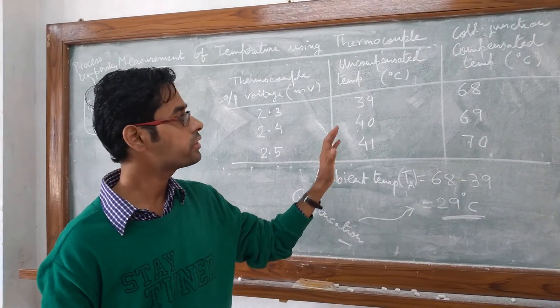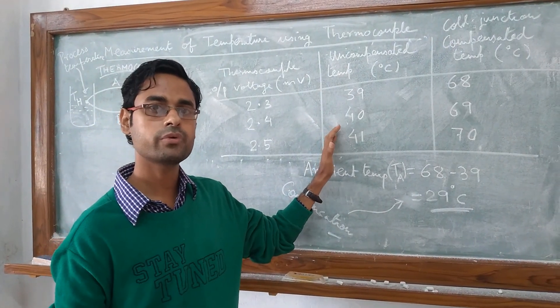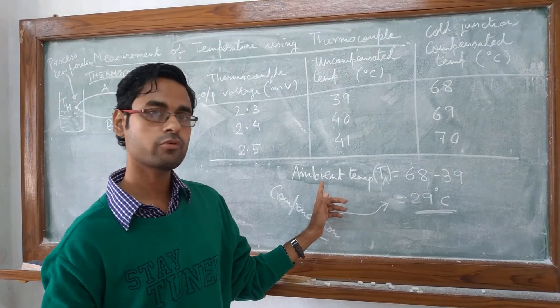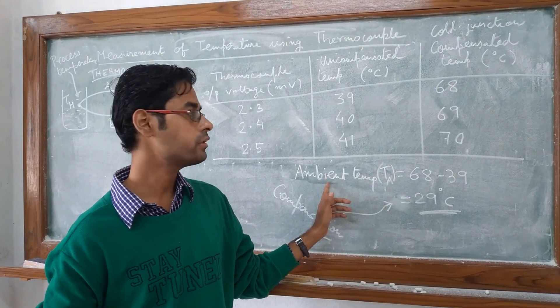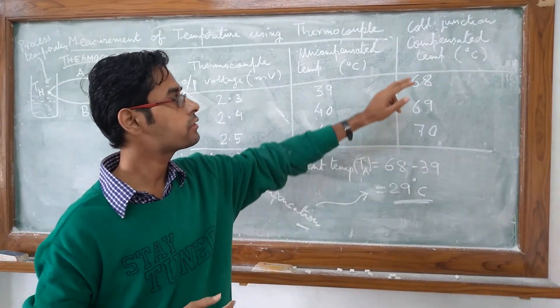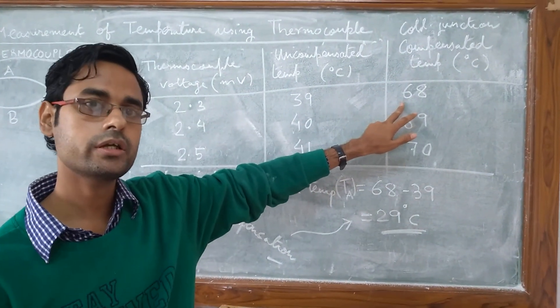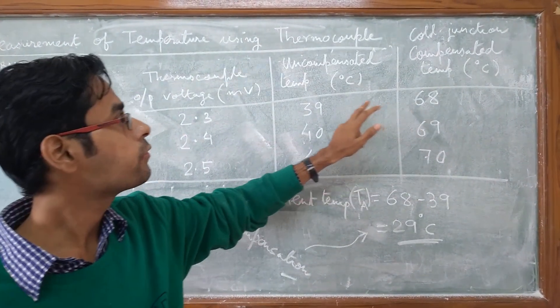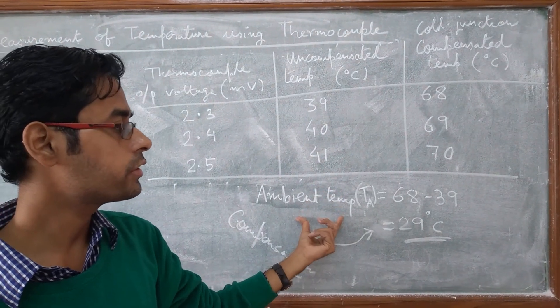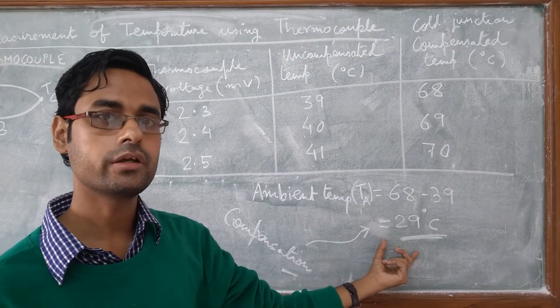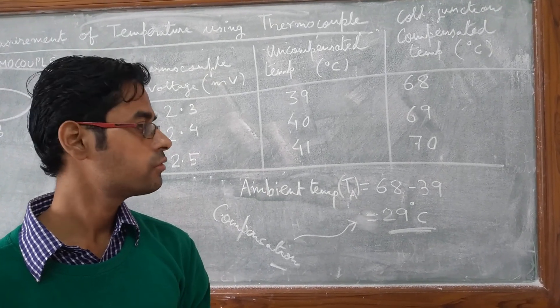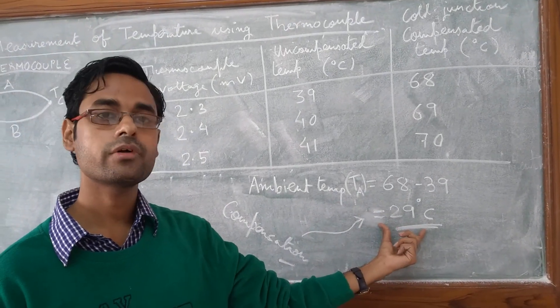So these were the set of readings that were obtained previously. And you can see that the compensation was provided for ambient temperature by the cold junction compensation circuit, where we found that the compensated temperature was 68 degree centigrade while the uncompensated temperature was 39 degree centigrade. So the ambient temperature was 29 degree centigrade. So the electronics module was providing for compensation for this value of ambient temperature.